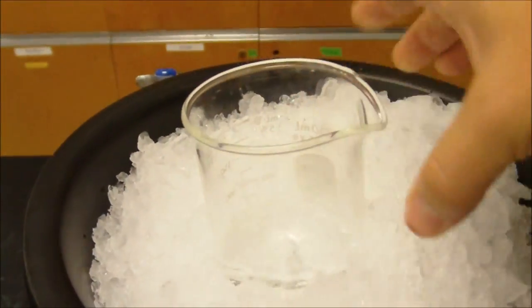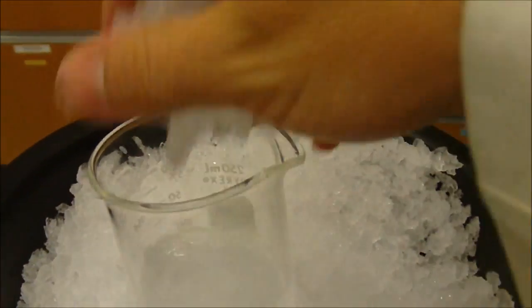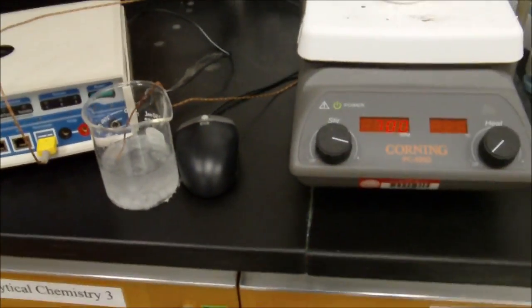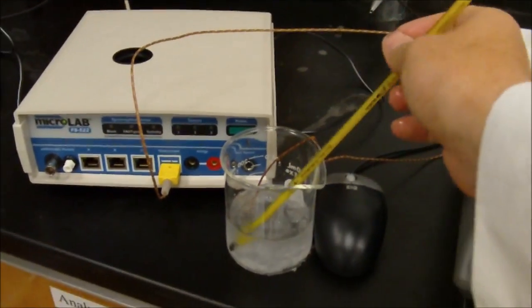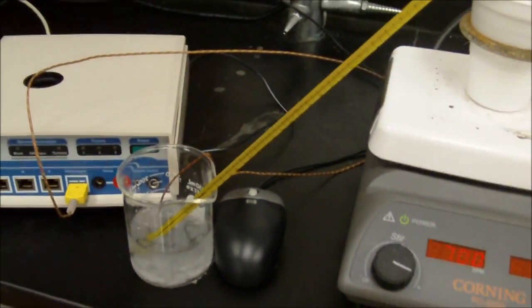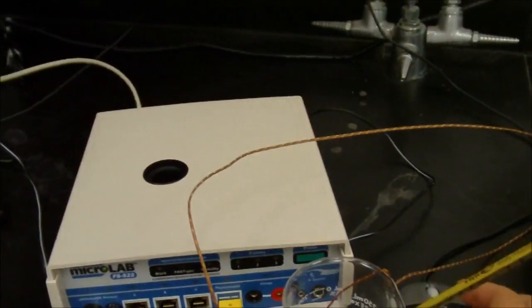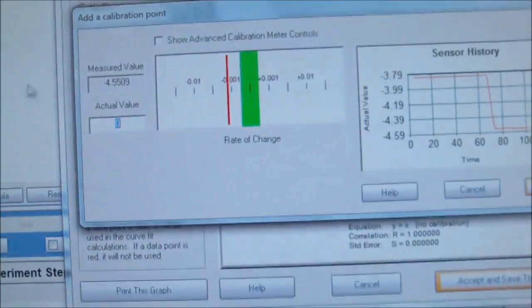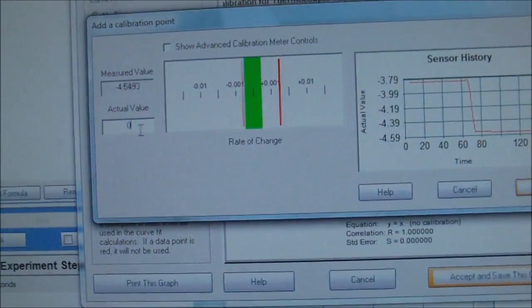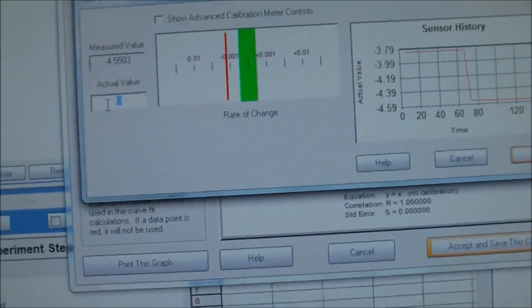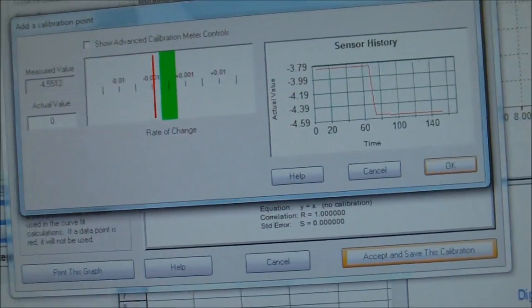This one we're going to do some ice water, right? Nice cold ice water. So we take our thermocouple, place it into the ice water. All right, put this into there. Wait for the temperature to stabilize on the thermometer. Okay, then we come back up here and we see that the thermometer says 0 degrees, so we change this, and you have to type in a 0.